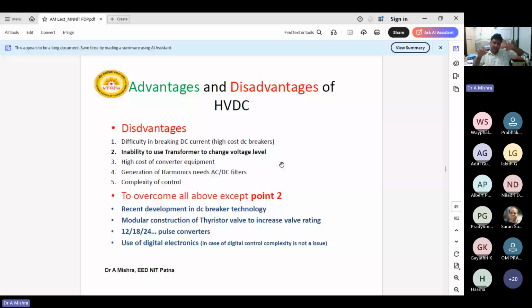Suppose there is a 6 pulse converter. One option is that you take a single piece of the 6 pulse converter. If there is any fault, you have to replace the whole system. But instead of that, use 6 modular different structures. If there is any kind of short circuit in any of your thyristor valves, then you change that particular valve. Modular structure means if there is any fault in any part of the system, it can be easily replaced. So modular construction is available for each and every component.